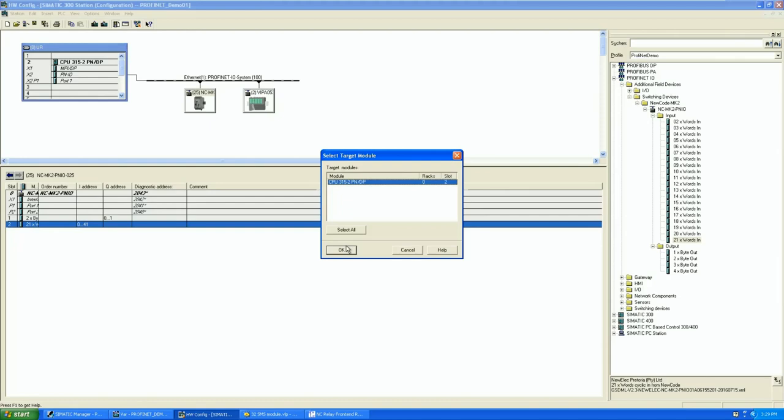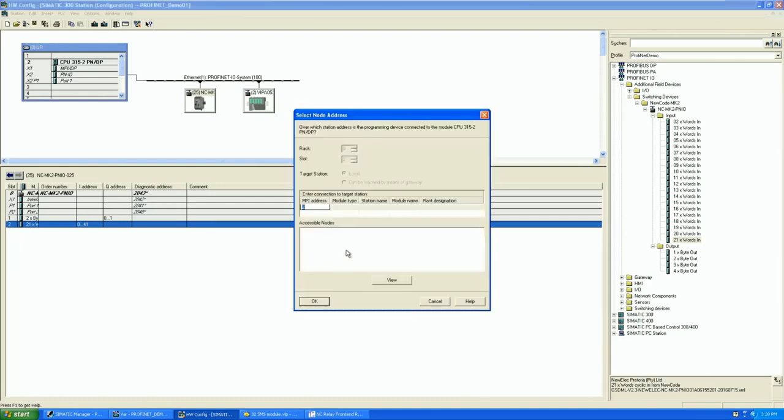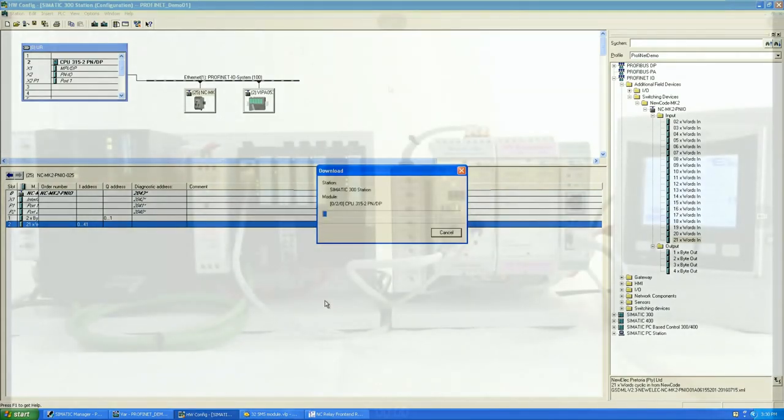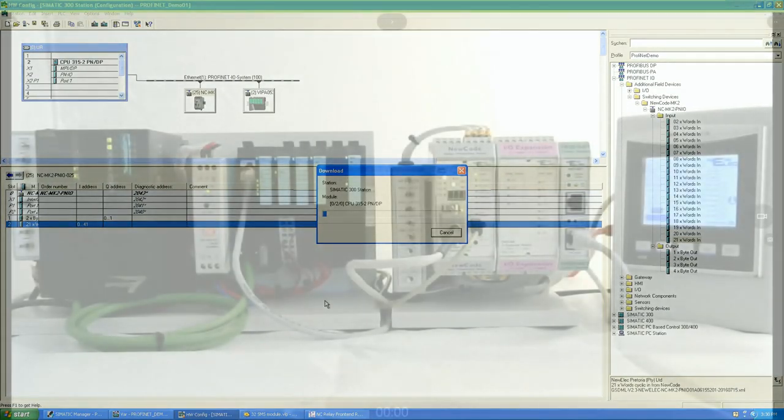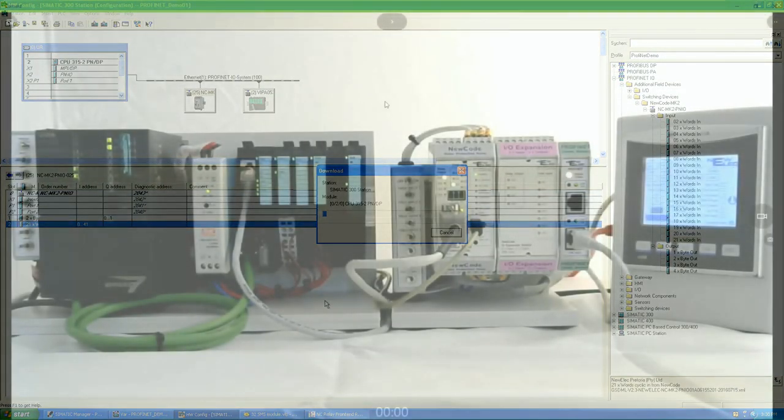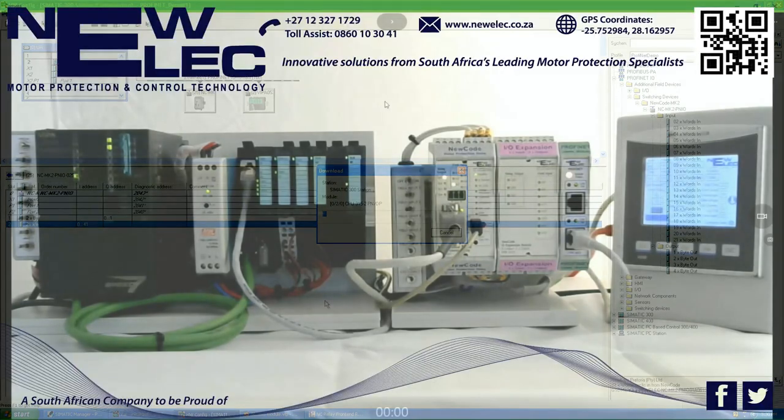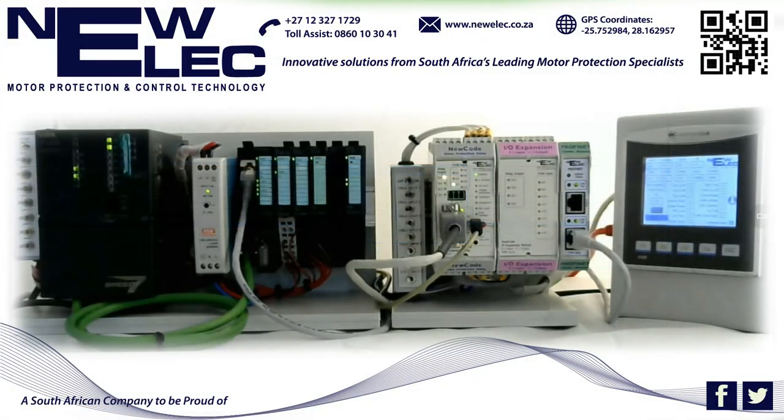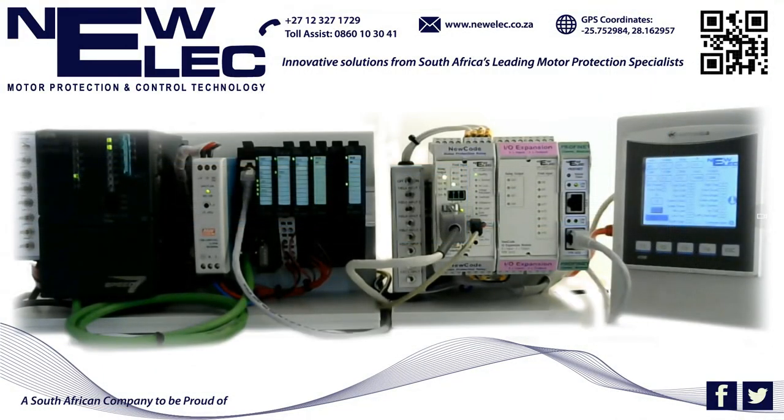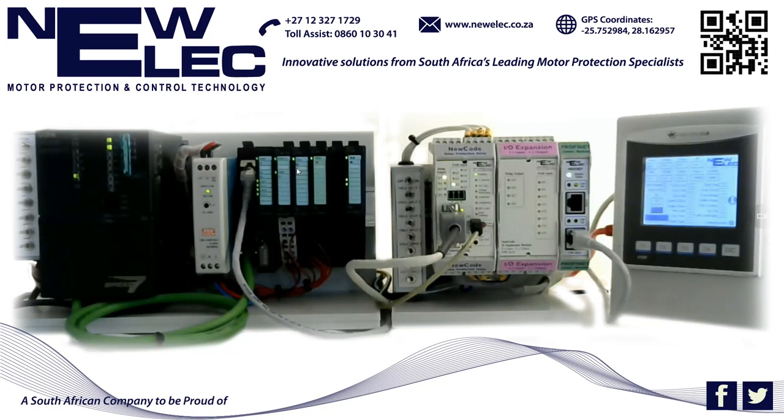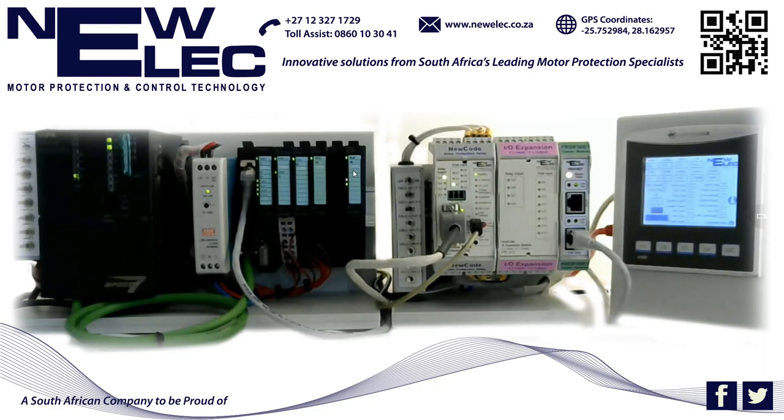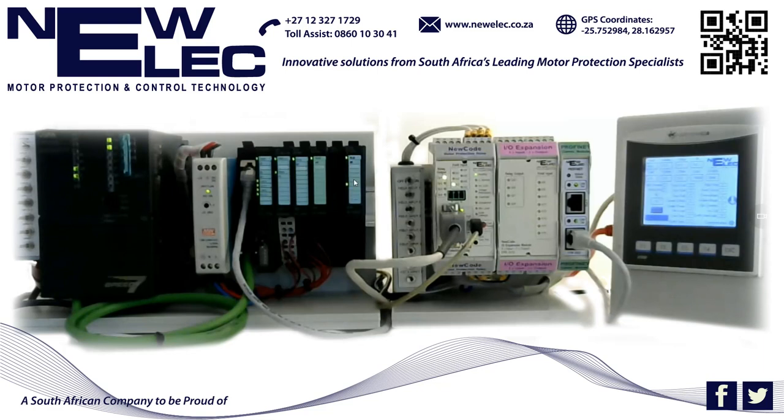To give a bit more of an in-depth look into what we've got configured here, currently on the field input module, input 1 is linked to the NewCode relay's relay 2 and input 2 is linked to the NewCode relay's relay 3. On the output module, output 1 is linked to the NewCode's field input 1, output 2 to field input 2, and this flashing LED currently here on output 3 is the heartbeat of the NewCode PROFINET module. On the 4th output, we've got the link status between the PROFINET module and the NewCode relay.